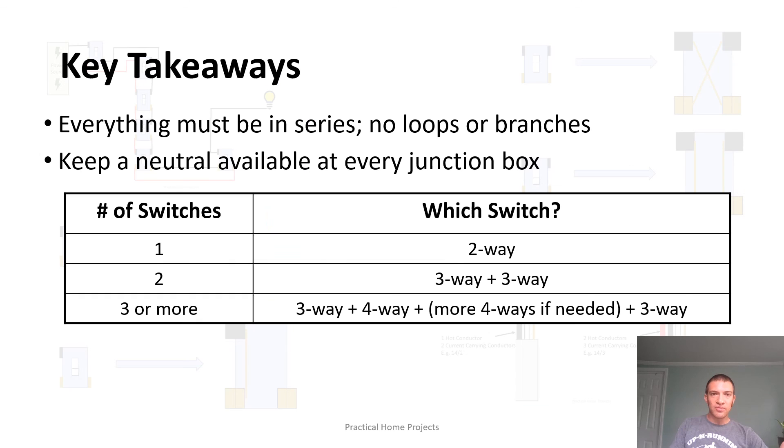And that's sort of the basics of what we have today, so let me go through the key takeaways. Everything must be in series. You have to have power source at the beginning and your device at the end. You can't add any loops, you can't add any branches. The best practice and what you have to do to follow the code going forward is to keep an actual neutral available in every single junction box. And then here I just have a table: if you only need one switch you can use a two-way. If you need two switches, you'll use a three-way for both of those. If you have three or more switches, you'll use a three-way on the ends and then as many four-ways as you need in the middle. So I really hope this helped you guys with setting up your new project.